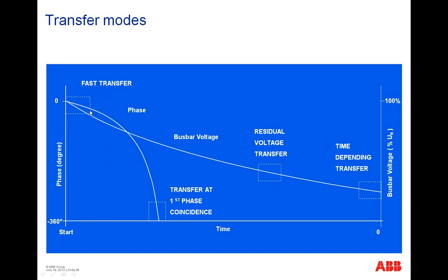But normally you always have the fast transfer. This is the main transfer mode if you have good protection, if you have breakers below 100 milliseconds, and with this fast transfer mode you keep all the processes alive. This is the big feature of the HSTD, to provide this here, this here, this here, and if you see this, this is the functionality of an ATS.